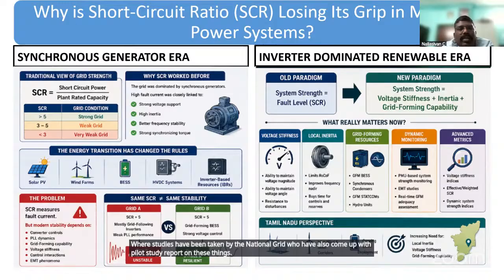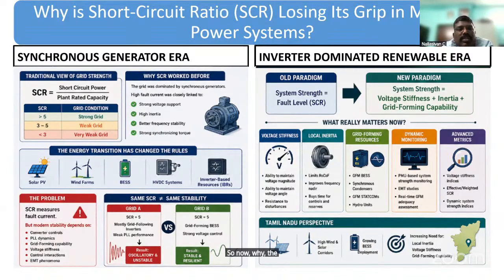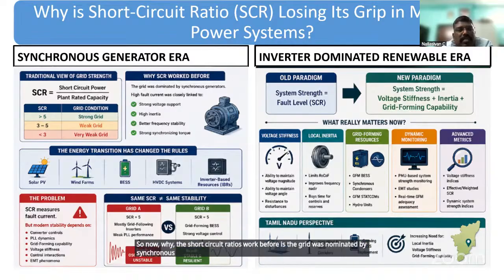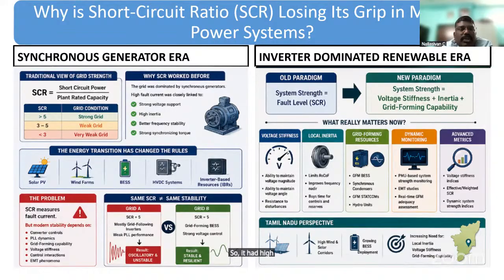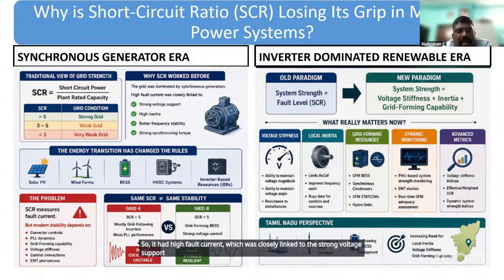Now, why did the short circuit ratio work before? Because the grid was dominated by synchronous generators, as highlighted. It had high fault current, closely linked to strong voltage support, firm power, high inertia, better frequency stability, and strong synchronizing torque.